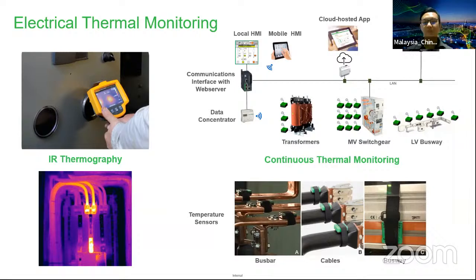So, for example, Schneider Electric has come up with a remote thermal sensor that is coupled with the characteristics of the equipment itself and constantly measures — the key point here is constantly measuring in real time — the temperature of a particular cable, busway, transformer, or any cubicle of your MV/LV distribution board.